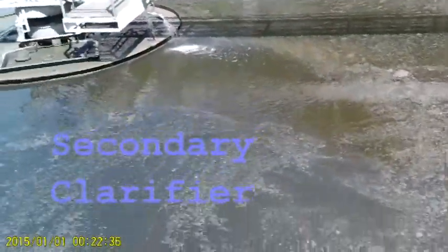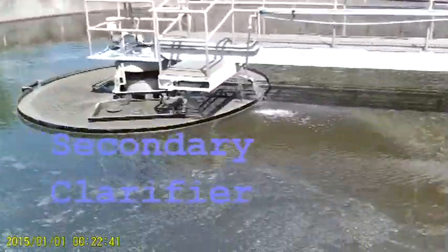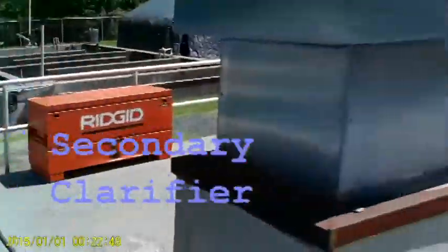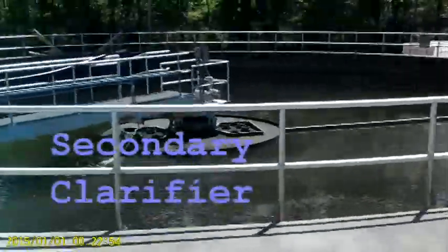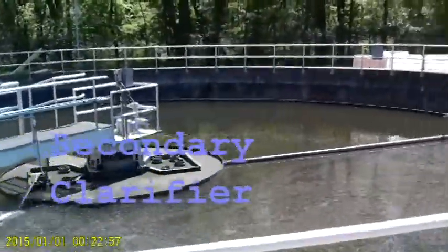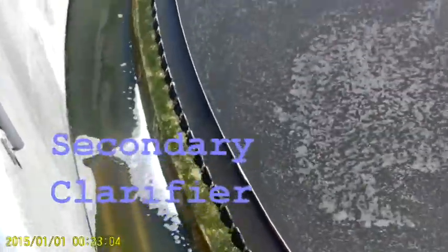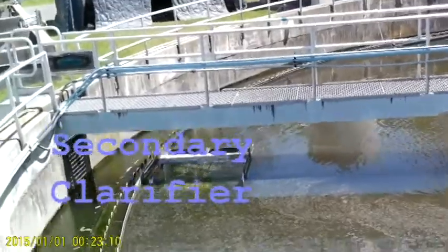This secondary clarifier is bigger in diameter than the primary clarifiers, and here the activated sludge settles to the bottom, and the clarified water, what we call effluent, rises to the top and goes over the V-notch weirs, which is now called secondary effluent. Here's the water going out of the plant onto the chlorine contact tanks for disinfection of E. coli and any pathogenic microorganisms.